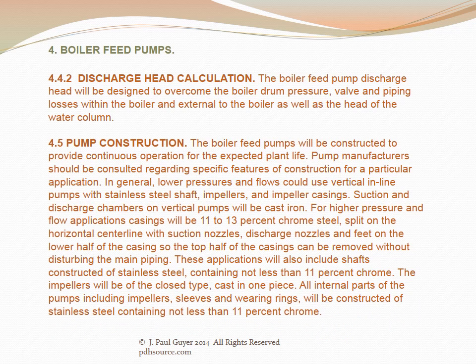The boiler feed pump discharge head will be designed to overcome the boiler drum pressure, valve and piping losses within and external to the boiler, as well as the head of the water column. For low pressures and flows, vertical inline pumps with stainless steel shaft impellers and impeller casings could be used. For higher pressure and flow applications, casings will be 11 to 13 percent chrome steel, split on the horizontal centerline with suction nozzles, discharge nozzles, and feet on the lower half so the top half can be removed without disturbing the main piping. Shafts will be stainless steel with not less than 11 percent chrome, impellers will be of the closed type cast in one piece, and all internal parts will be stainless steel containing not less than 11 percent chrome.